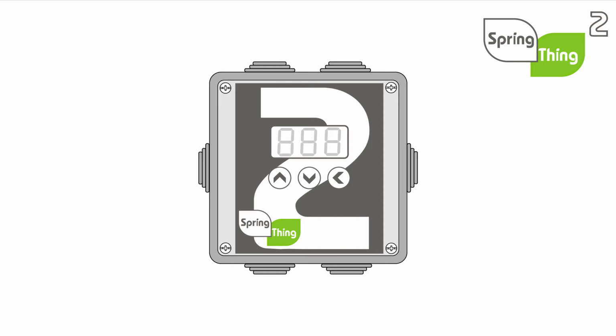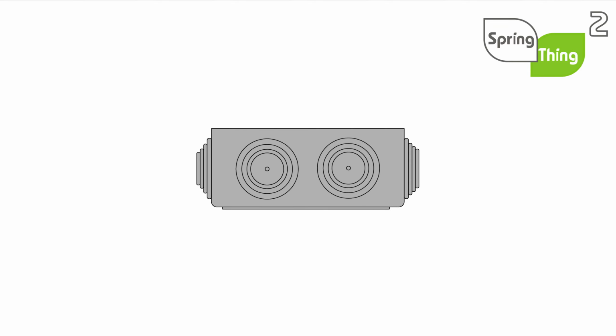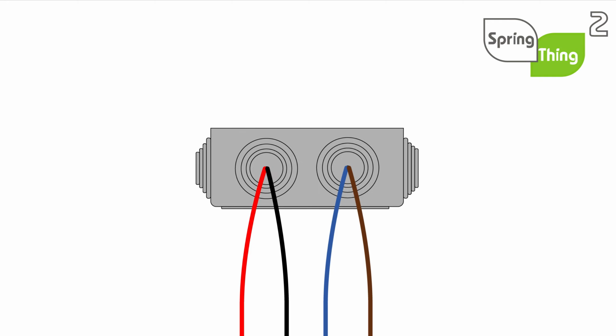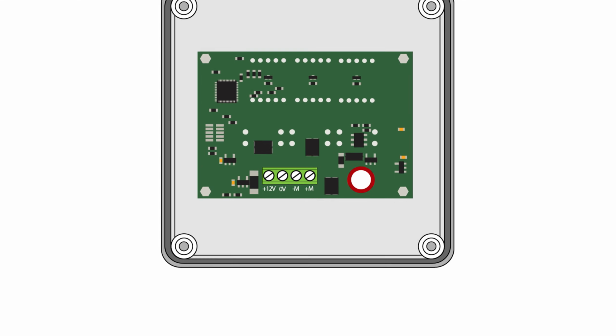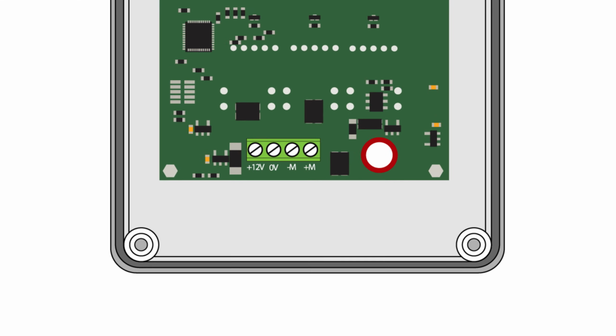Follow these steps to connect the wires. We recommend 1 mm squared tri-rated cable is used. Before wiring the controller, pierce the 2 flexi glands at the bottom of the controller using a sharp pointed object, such as a screwdriver. Then push the wires through the glands. Spring recommends the following wire colours. These are available as an optional spring wire and fuse kit.